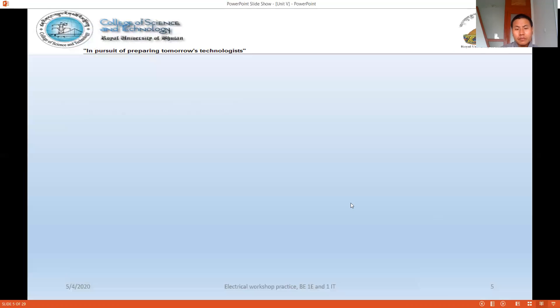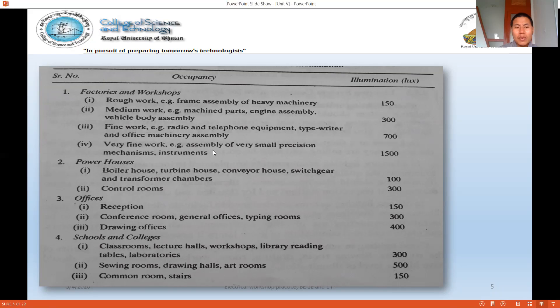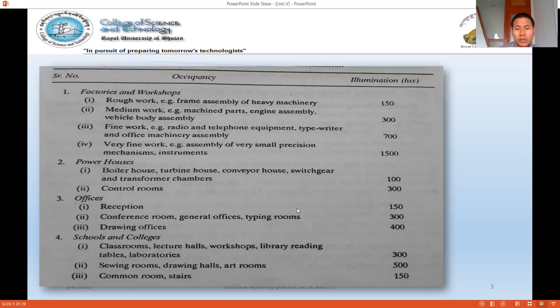The required illumination standards in lux are as follows: for factories and workshops doing rough work, 150 lux; medium work like engine assembly or vehicle body assembly, 300 lux; fine work like radio/telephone equipment or typewriter assembly, 700 lux; very fine work such as assembly of small precision instruments and electronics chips, 1500 lux; and for powerhouses like boiler houses, turbine houses, conveyor houses, and switchgear and transformer chambers, less illumination is required.